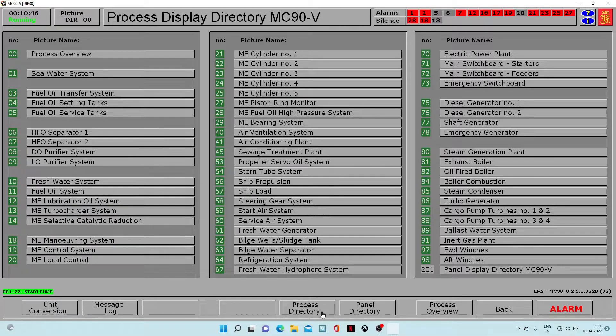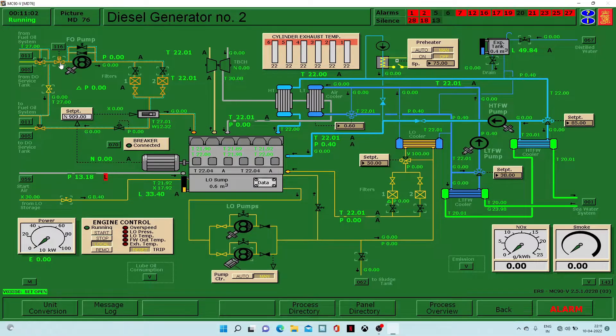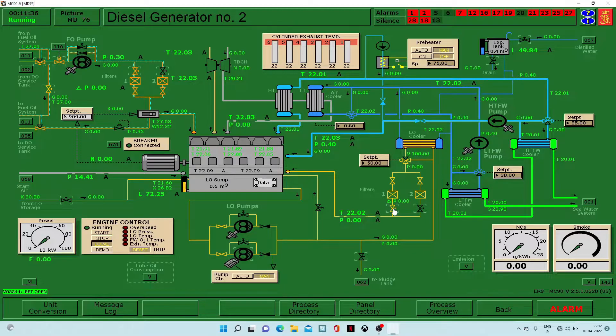Now we can start diesel generator two. Before starting, the checks we need to do: first, fill the lube oil level in the sump to 70, and meanwhile turn on the fuel oil valves — diesel fuel oil valves going to the pump and the filter. The diesel fuel from the service tank was already opened during diesel generator one setup, so no need to repeat that. Sea water, fresh water pumps are already running and starting air is already coming. We close the sump valve when the level reaches 72, open the valve going to filters, and start the pump.